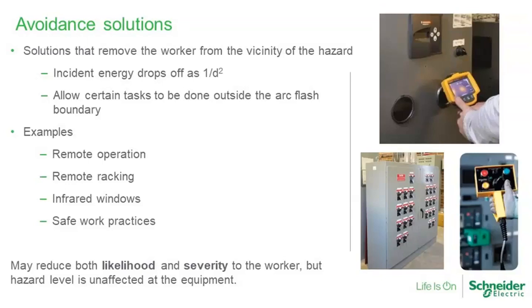Again, several examples of this: remote operation, remote racking, infrared windows or embedded thermal sensors. I have the infrared windows shown up there on the top right, so you can do your thermographic scanning without having to remove covers on energized equipment. The newest trend in this area would be embedded thermal sensors, wireless sensors that you can put inside the equipment to get the same data out on a continuous basis. You're not opening the covers, you're not exposing someone to the hazardous energy, and so we can reduce both the likelihood and the severity to the worker. One consideration, and we'll come back to this later: the hazard level will be unaffected at the equipment itself. If you're trying to protect your equipment from potential damage, this may not be the way to go.